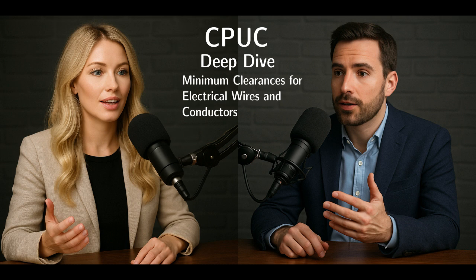The rules keep evolving, right? Yeah. They even cover newer stuff. They do. The tables have specific entries now for things like uncovered, grounded, non-dielectric fiber optic cables. Okay, what does that mean in plain English? Fiber optic cables that aren't fully insulated. Pretty much, yeah. Fiber cables that might have some metallic component or aren't designed to resist electrical contact. They need 15 inches from other communication lines, but 120 inches, 10 feet, from those high voltage 300 to 550 kV lines. Huge difference again.